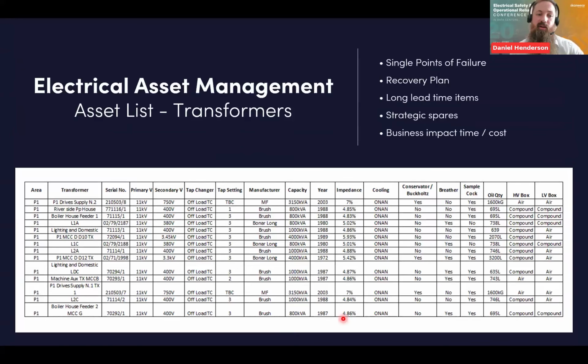Just taking this a little bit further into transformers, same process. I'd still be doing my single points of failure, looking at those recovery plans, but other items I'd start looking at would be things like long lead time items. We all know how long it takes to procure a bit of electrical equipment. You're talking 12 to 20 weeks, depending what it is, sometimes longer if it's more unique, which is why some of the things I'd be looking at typically here would be primary and secondary voltage, and the size or the capacity of the transformer.